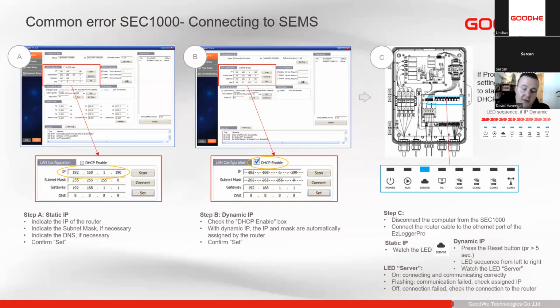If you do that, I always recommend take a Koki pen or something like that, and in the lid of the SEC, open it up and write the IP address there. So if in the future you need to come back to site and do anything, all you have to do is plug into the network, put that IP address into the ProMate and press connect. You don't have to change anything, you don't have to reset anything, it will just work.